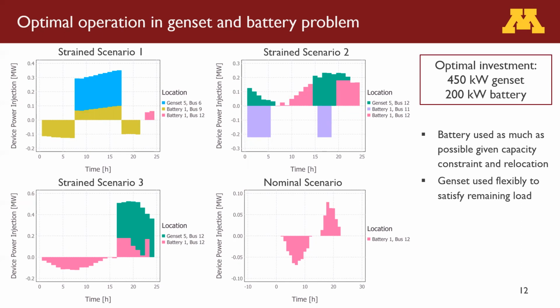Whereas the genset serves a supporting role, where it satisfies all of the load or all of the demand that the battery cannot satisfy while being used as much as possible. So in scenario 1, it covers this additional load that can't be covered by the battery in this middle period. And in scenario 2, it's used for any time period where the battery is either charging or relocating.